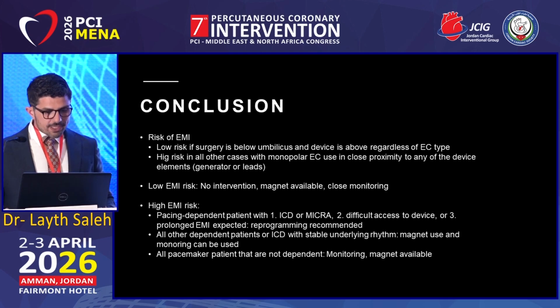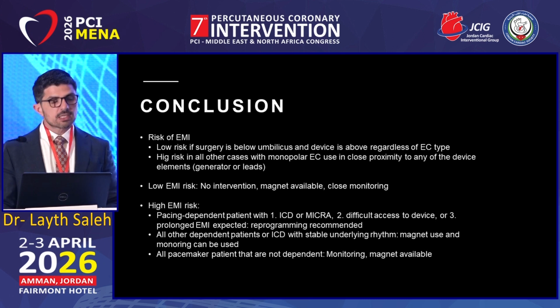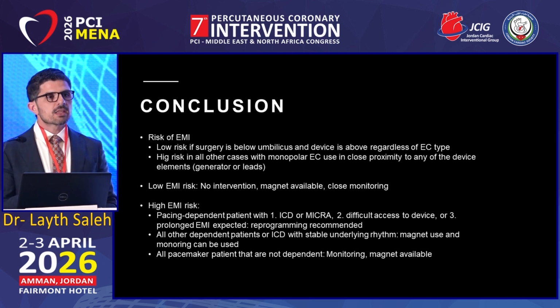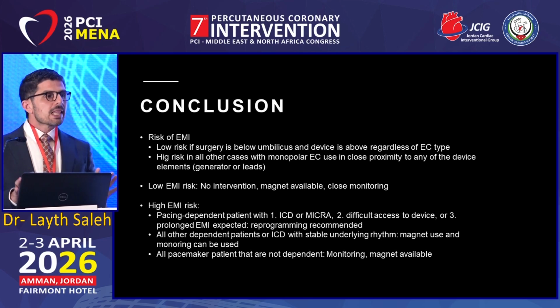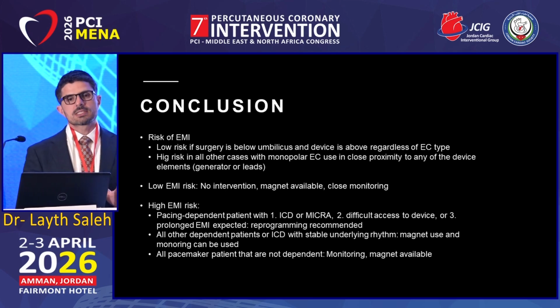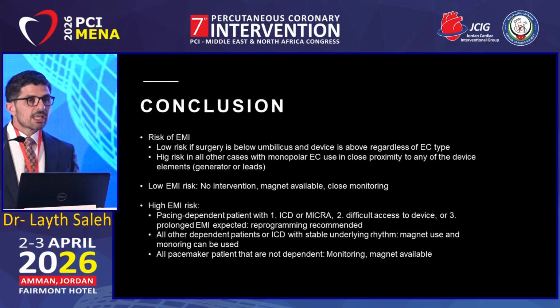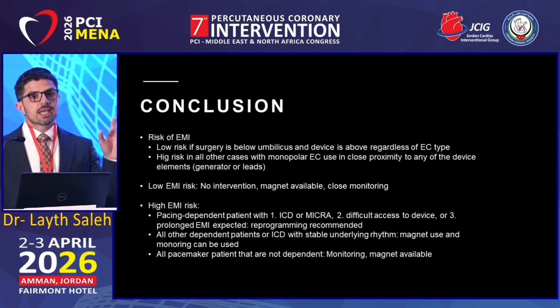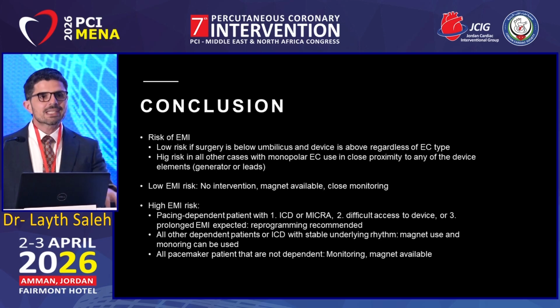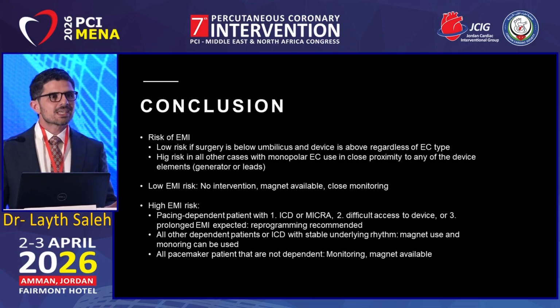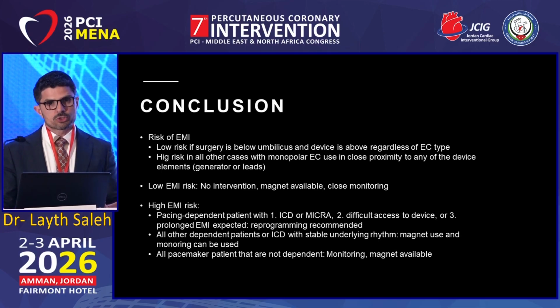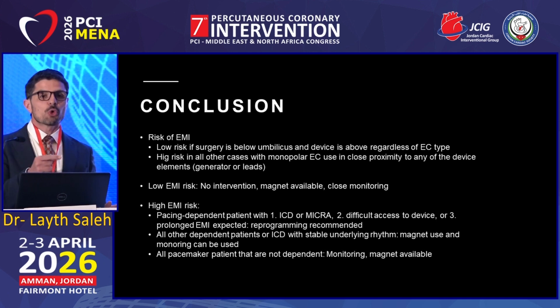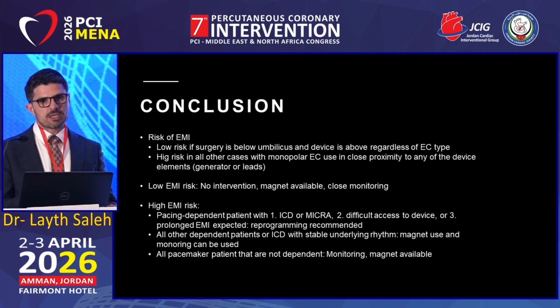And then lastly, all pacemaker patients who are not dependent, you can monitor with magnets being in the room without intervention. Last thing I want to mention really quickly, and I know that many of you probably know this: magnet function in an ICD, regardless of whether it's dual chamber, single chamber, CRT-D. If there's an ICD, what the magnet does is disable tachycardia therapy, with no effect on the pacing algorithm or mode. So if the patient is dependent, you always have to reprogram the patient before if there's risk of EMI.